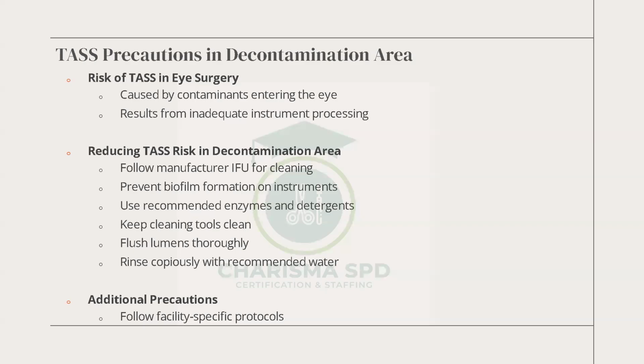Results from inadequate instrument processing. Reducing TASS risk in the decontamination area. Follow manufacturer IFU for cleaning. Prevent biofilm formation on instruments. Use recommended enzymes and detergents. Keep cleaning tools clean. Flush lumen thoroughly. Rinse copiously with recommended water. Additional precautions: follow facility-specific protocols.